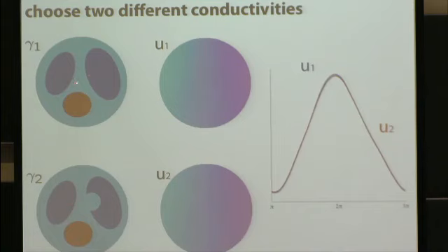So what happens in both cases is that this is the conductivity. Then I apply a voltage. Here's a positive voltage. Here it goes to negative, and 0 here, and again positive. And at the boundary, I put the same voltage here and here. Inside, we see this is the potential inside, but that's something we cannot measure. We measure at the boundary.